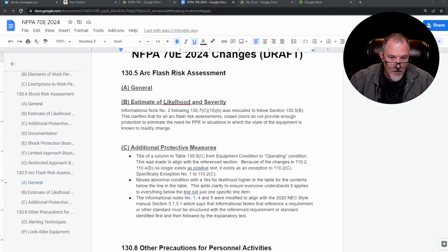The informational note number 2 was relocated to follow section 130.5(B). This clarifies that for all arc flash risk assessments, closed doors do not provide enough protection to eliminate the need for PPE in situations in which the state of the equipment is known to readily change. It goes right into the section on estimate of likelihood and severity. So here's the issue.